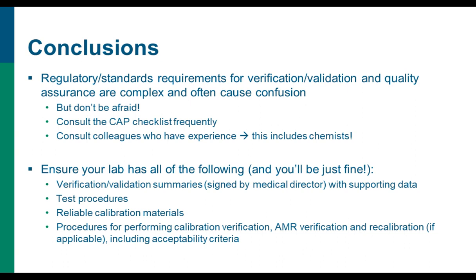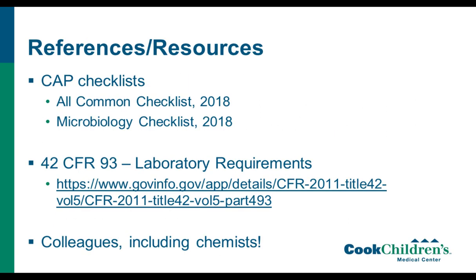And make sure that you have a procedure, either in your specific test procedure or a specific procedure, for how you're going to perform calibration verification, AMR verification if necessary, and recalibration. Make sure you have what samples or what calibration panel you're using, what the acceptability criteria are for that, and what you're going to do if it fails. That's one of the big things: CAP doesn't specify the acceptability criteria, but you must have them and you must develop them as a lab. So if you have all that, you'll be just fine. It's not as hard as it seems. Once you get going, it gets a little easier.